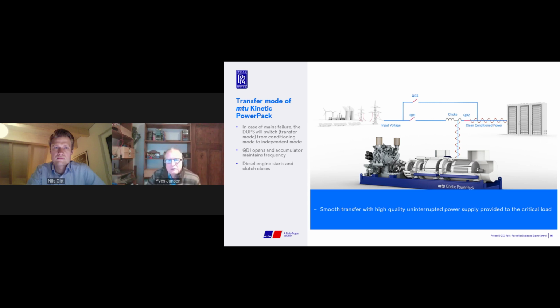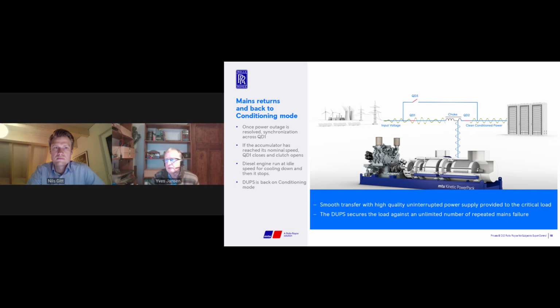In case of mains failure, the dynamic UPS will switch from conditioning mode to independent mode. And how does it do that? Simply by giving the instruction to open the circuit breaker QD1. At this stage, the accumulator, the accu, will maintain the frequency, so the speed of the main shaft. The diesel engine starts and the clutch closes. We have a smooth transfer of the power supply, with high quality uninterruptible power supply provided to the critical load.